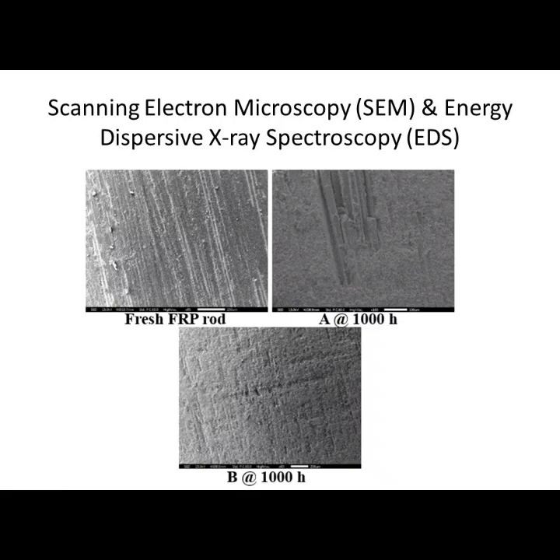For the fresh sample here, we see that the glass fibers are well covered by the epoxy resin matrix, and also the interface between the glass fiber and the epoxy resin is intact. However, after the experiment, the normal FRP rod, sample A, shows a severe degradation where many glass fibers are found to be broken and separated from the epoxy resin matrix, and the remaining epoxy resin matrix was found to be uneven and elastic with many holes, which could be due to the gas generated during the degradation of the epoxy resin under the impact of the electrical discharges, arcs, leakage current, etc.